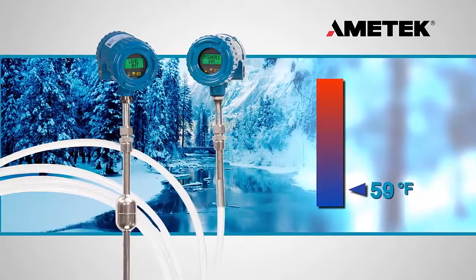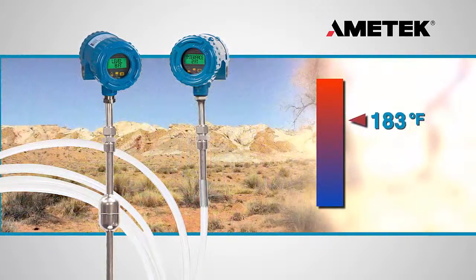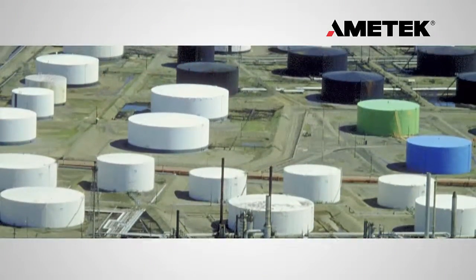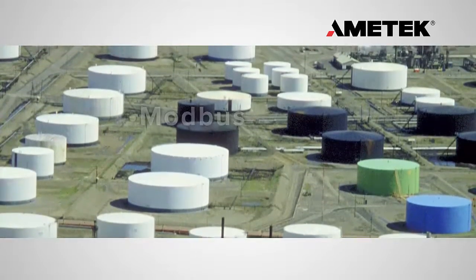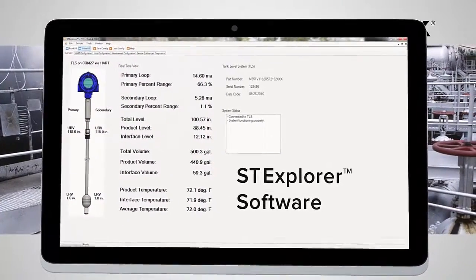In addition, the Drexelbrook Total Tank Level System is fully compensated across the entire operating range of process temperatures, up to 257 degrees Fahrenheit. The system easily integrates into existing control systems that have standard protocols such as Modbus, 4 to 20 milliamp loop, or HART communications. Each instrument can be set up directly through the Ametek ST Explorer software, which can be downloaded free of charge from our website.